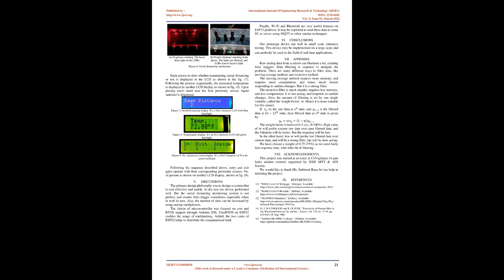A high value of W will prefer current raw data over past filtered data, resulting in lower filtration but a faster response. On the other hand, a low W will prefer the last filtered data over current data, giving a stronger filter but slower response. We chose a weight of 0.75, or 75%, to get a fairly fast response time with a bit of filtering.